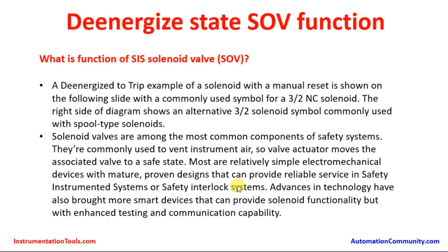Advances in technology have also brought smarter devices that can provide solenoid functionality but with enhanced testing and communication capability. Modern devices come with more built-in intelligent features which can detect solenoid operations and healthiness, and any internal failures in the solenoid component as well as in the actuator and pneumatic components. Those are fitted with smart devices.